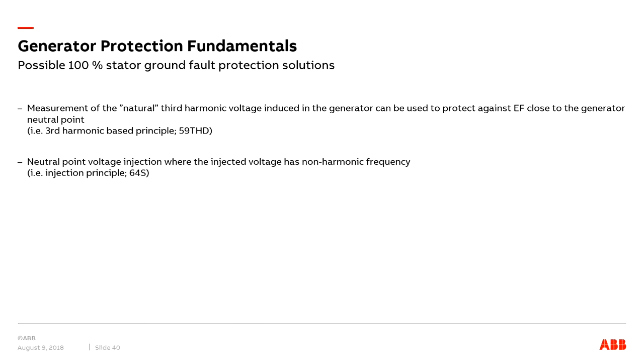There are possibly two methods to do that. As I mentioned, it is critical to detect and clear a stator ground fault close to the generator neutral. However, this is impossible to do with a simple residual overcurrent or residual voltage ground fault protection only. And because of that, we have this method of 100% stator ground fault protection.